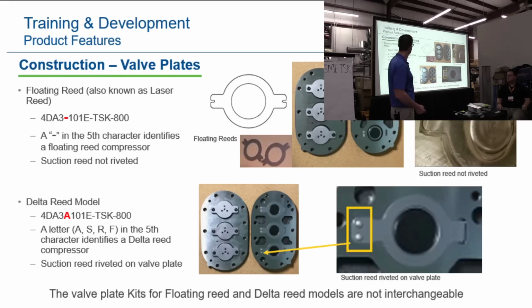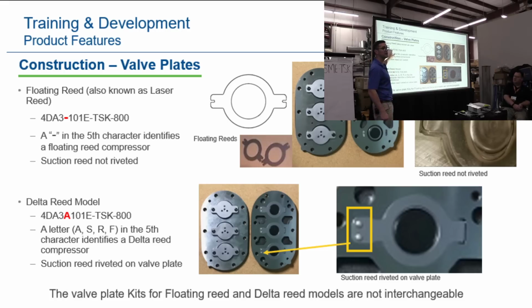Okay, excellent. Construction of the valve plate. So we have two different designs. We got floating reed. Has anybody seen floating reed design when they pull off a head before? Okay, then we got delta reed. These ones here are riveted on, and it all depends on the model number. You can't switch these. If it's a floating reed, you have to go with a floating reed plate on that compressor. If it's a delta reed, you have to go with the delta reed.